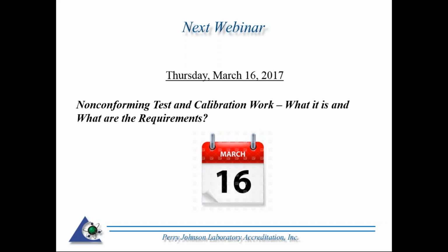Well, if I'm not mistaken, that is under 7.5 technical records. I'm sorry, 7.11 is control of data. That's information management. And actually, it's also specified on this slide under which section that was covered. The big change in there is if you altered off-the-shelf software, then you have to validate it again.